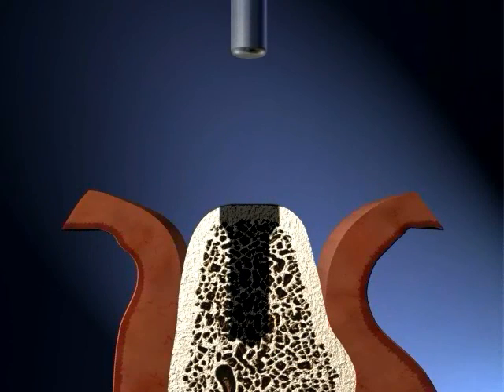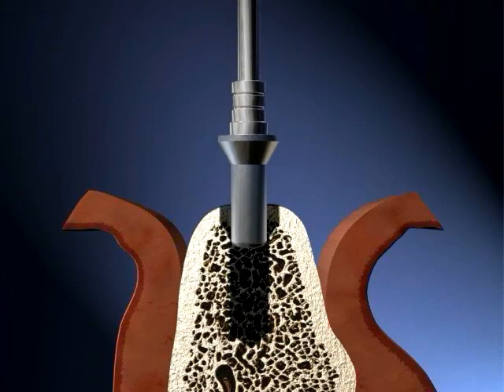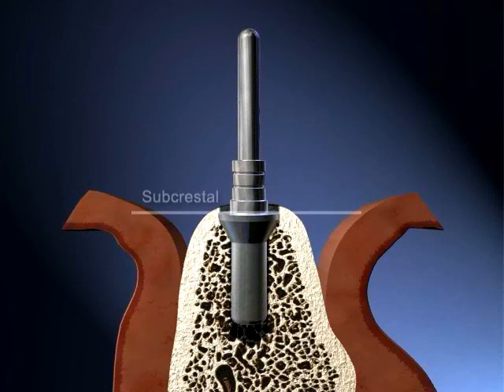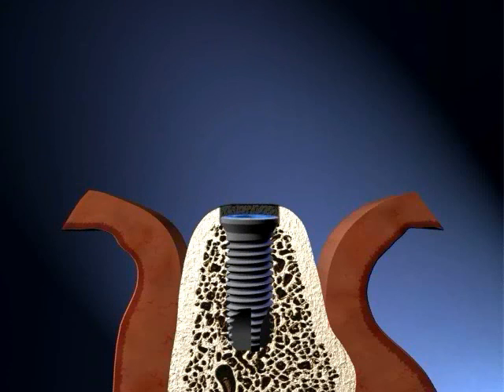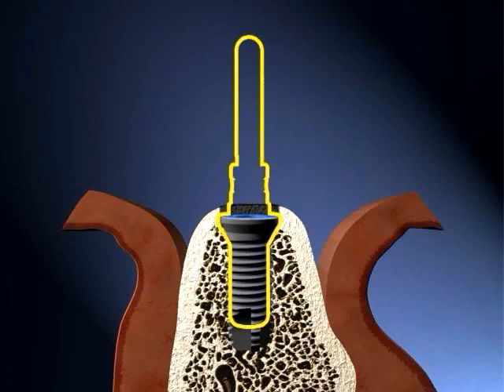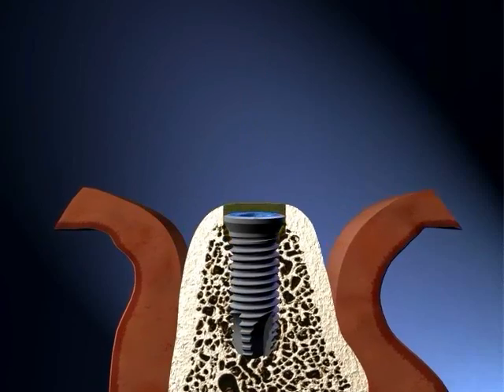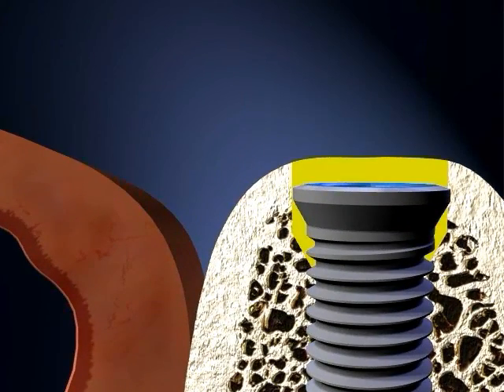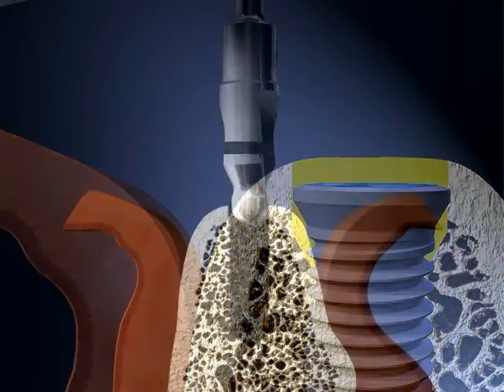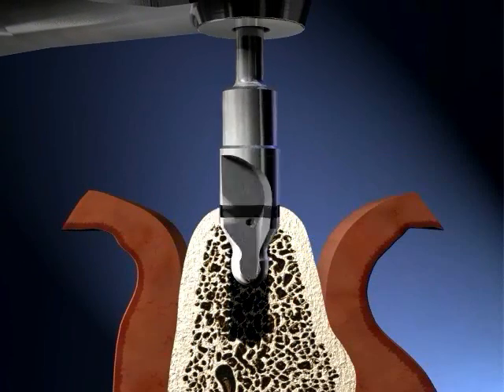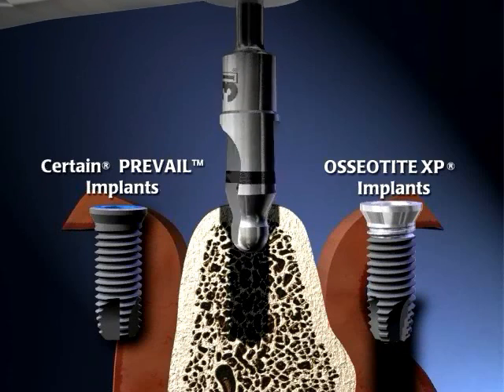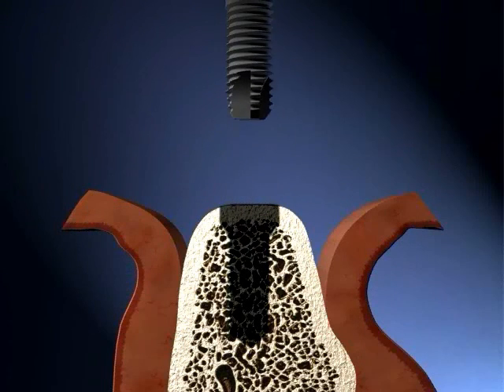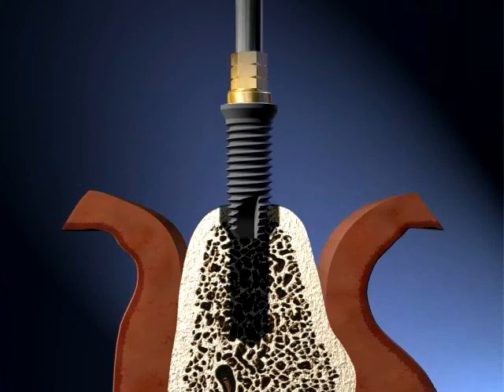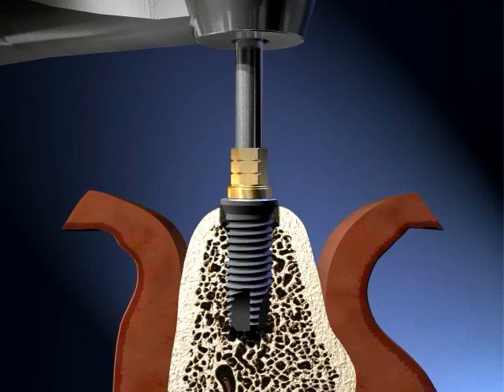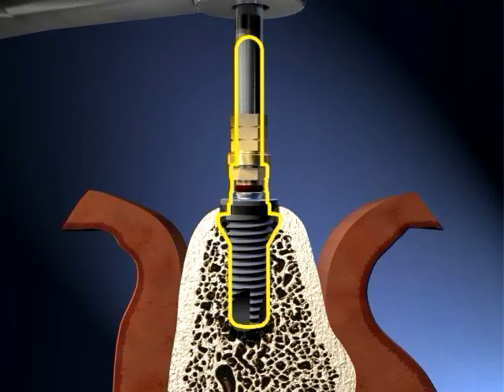The countersink depth indicators are used to simulate the implant platform prior to placing the implant. To ensure proper engagement of the implant collar, it must be seated to the depth demonstrated by the countersink depth indicator, or there is a risk of a poor fit between the implant and osteotomy. The countersink depth indicators can be used with the countersink drills when placing both certain PREVAIL implants and OsseoTite XP implants. When placing, the implant platform should reach the same position that the countersink depth indicator platform previously attained.